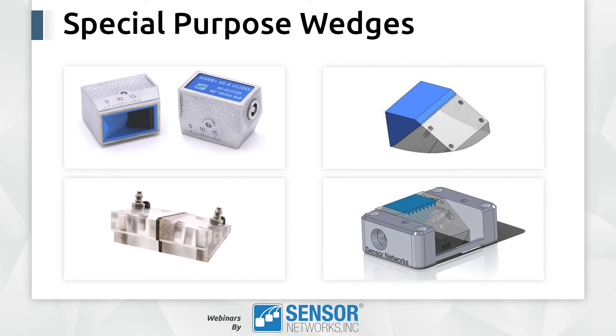Along with flat and radius probes, there are a lot of special purpose wedges out there. As you can see on this slide, there are integral wedges to the transducers themselves, both for phased array and conventional. There are many different varieties of phased array wedges — either skewed or multi-radiused wedges — as well as dual wedges with irrigation ports. And there are wedges with different ring assemblies or gimbal mounting points to be used in scanners or different fixtures.